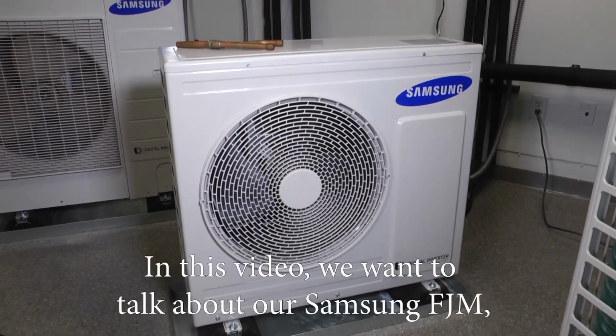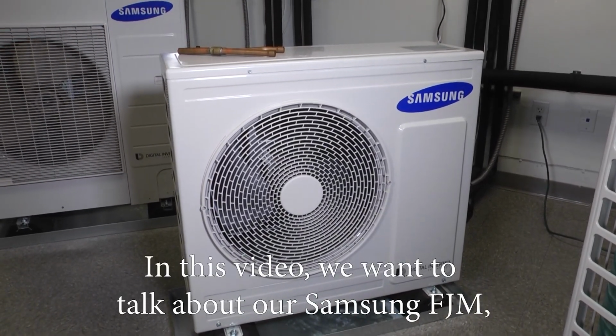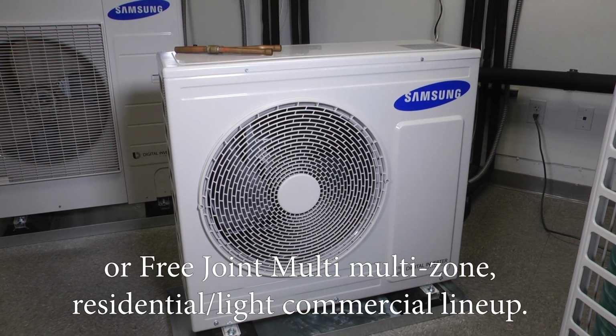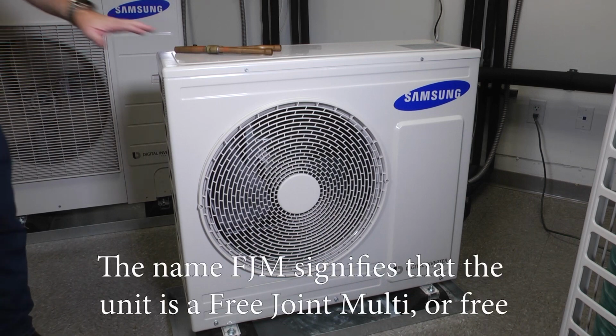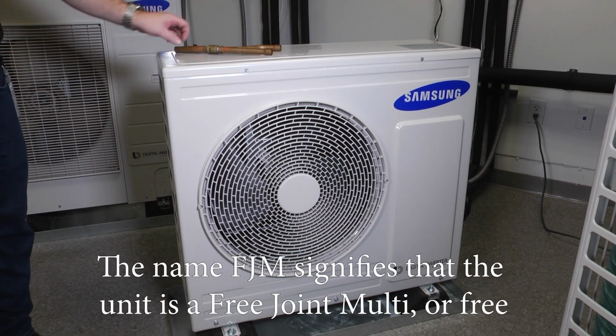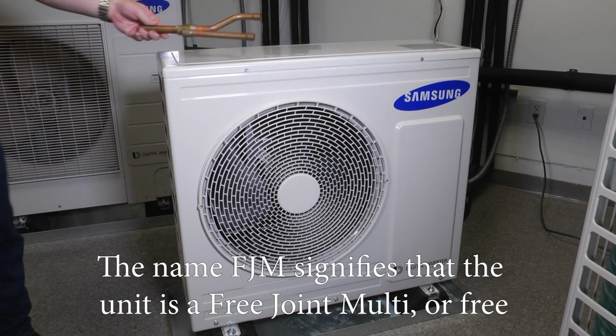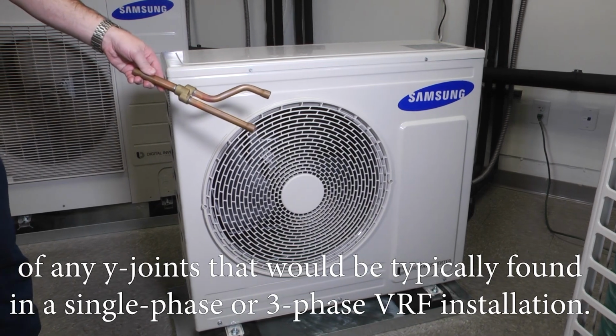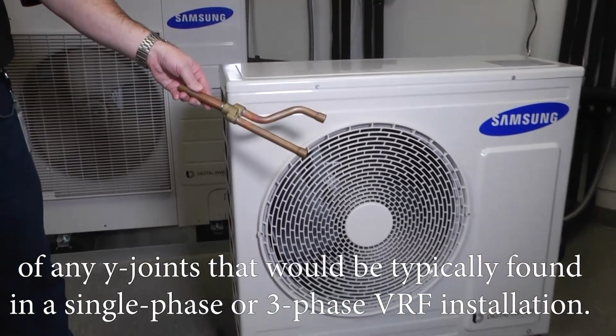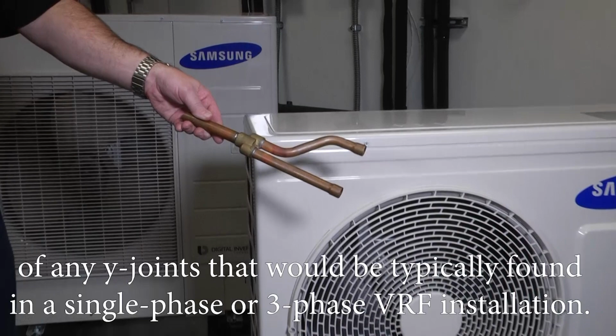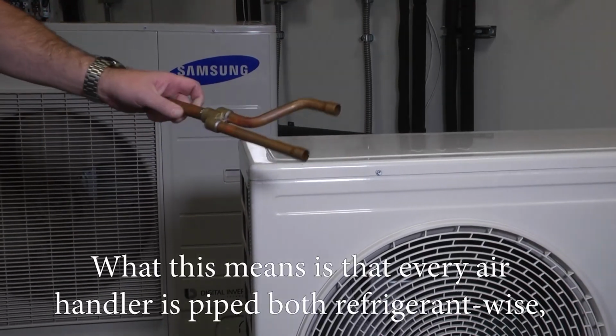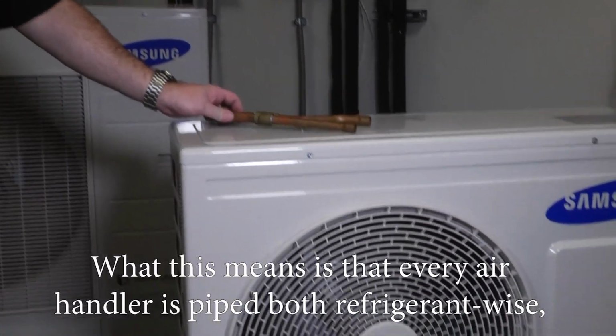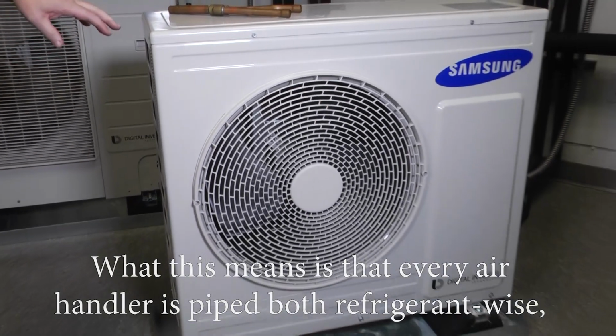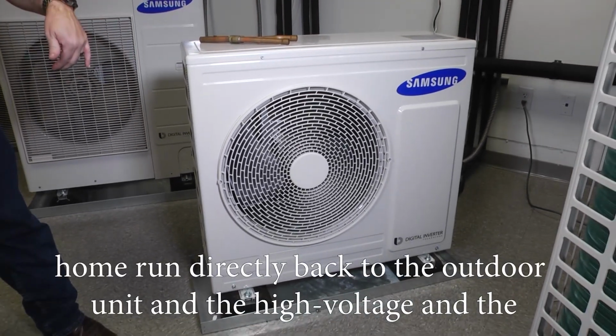In this video, we want to talk about our Samsung FJM, or Free Joint Multi-Zone Residential Light Commercial lineup. The name FJM signifies that the unit is a free joint multi, or free of any y-joints that would be typically found in a single-phase or three-phase VRF installation.